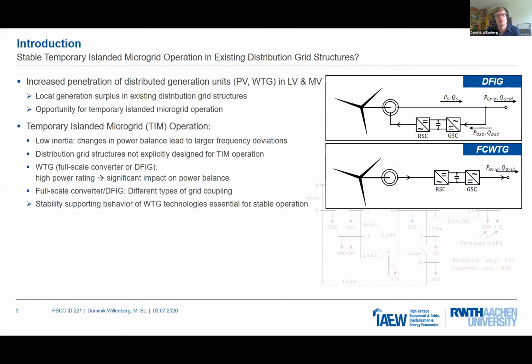If we now think about this temporary island microgrid operation, there are quite some differences if we compare it to the normal grid parallel operation. So first, there's strongly lower inertia, which leads to the situation that changes in the power balance may lead to larger frequency deviations. And also, these distribution grid structures are usually not designed for the temporary island microgrid operation.